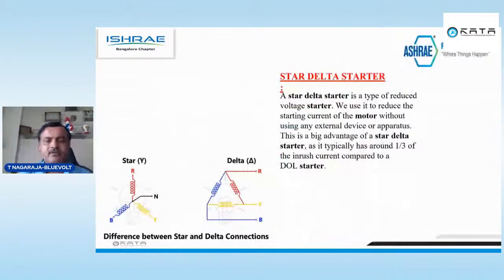This second one is the star delta starter. With a star delta starter, since the load is higher, your motor will start from 30 to 40% load in star, or a maximum of 50%. Suppose your motor is 15 kilowatt. When you press that button, it will start in star mode at 50%. Once it starts at 50%, your inrush current will come down. Instead of 6 to 8 times, it may go to 4 to 5 times.